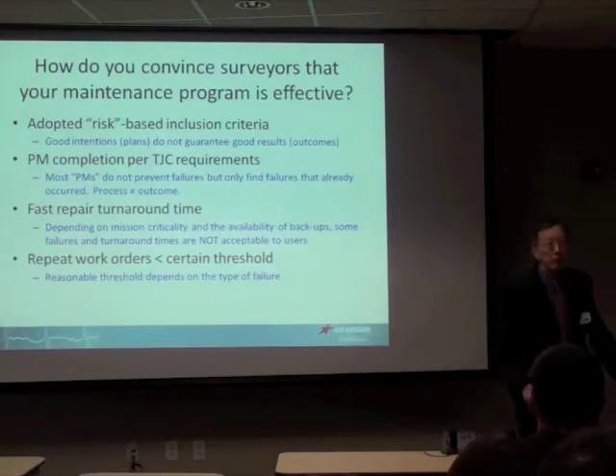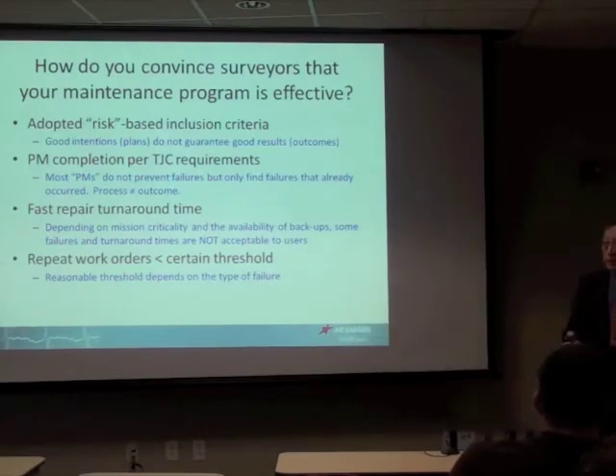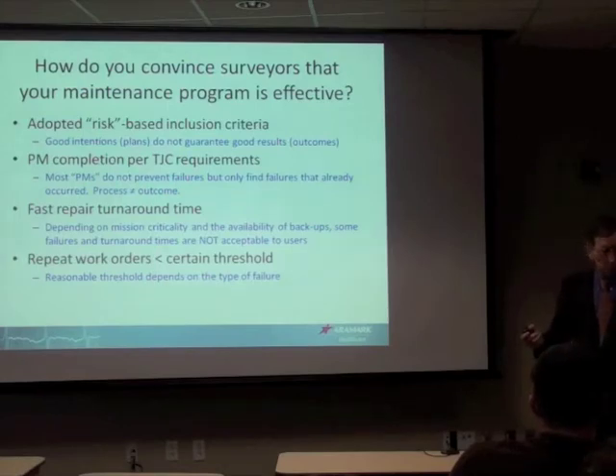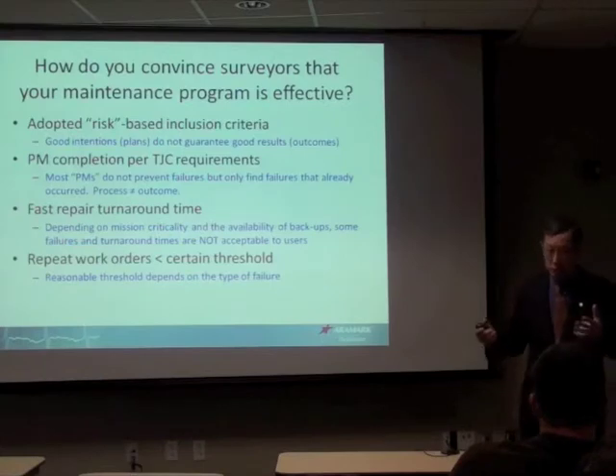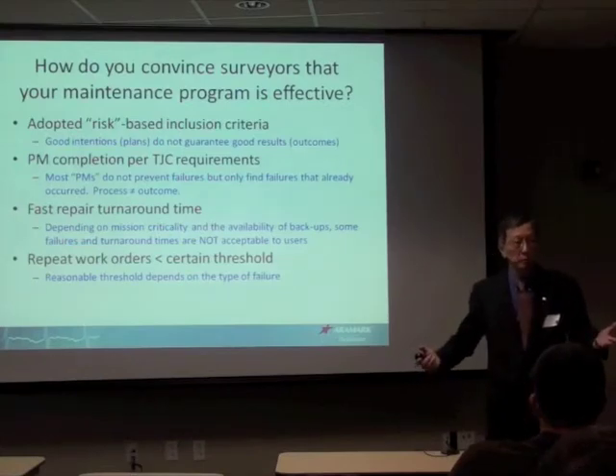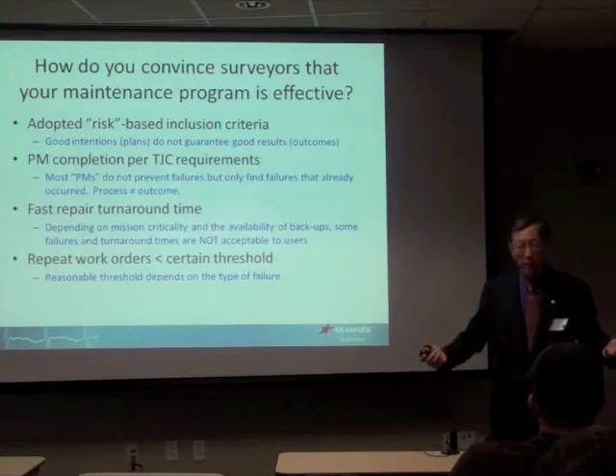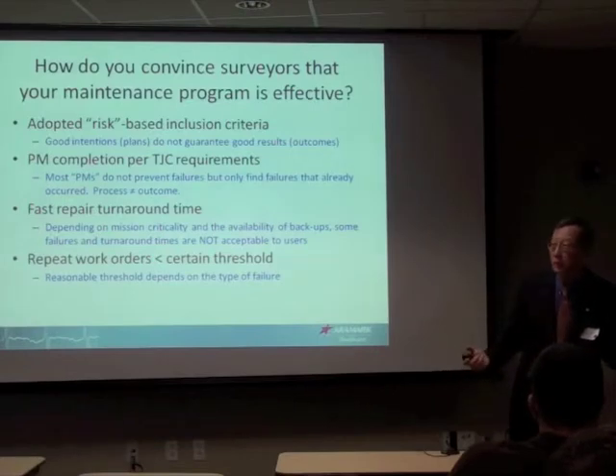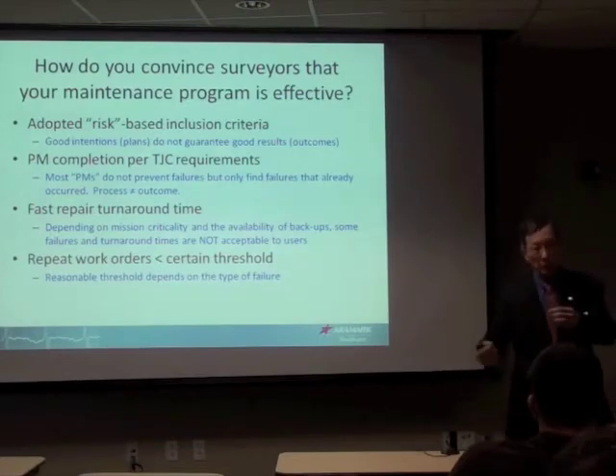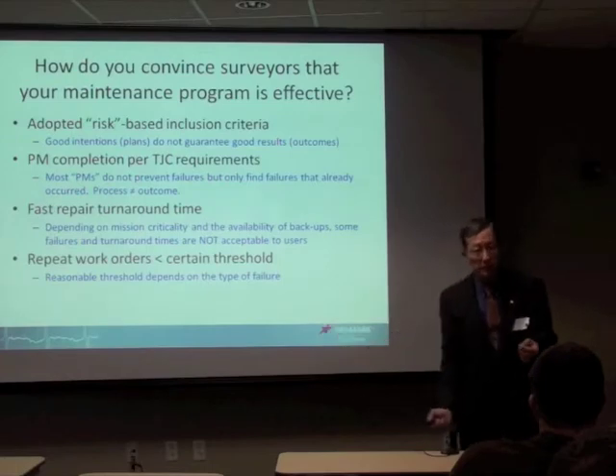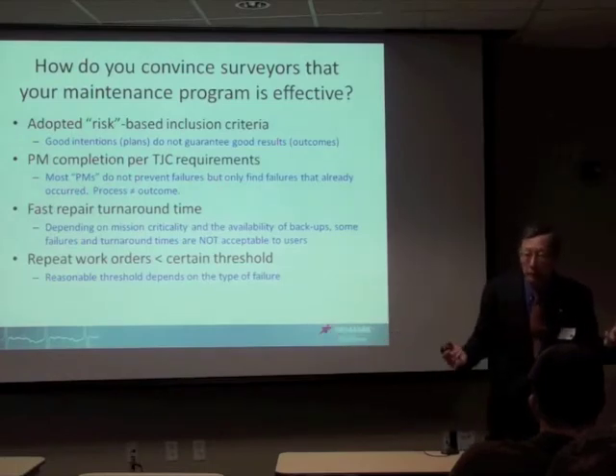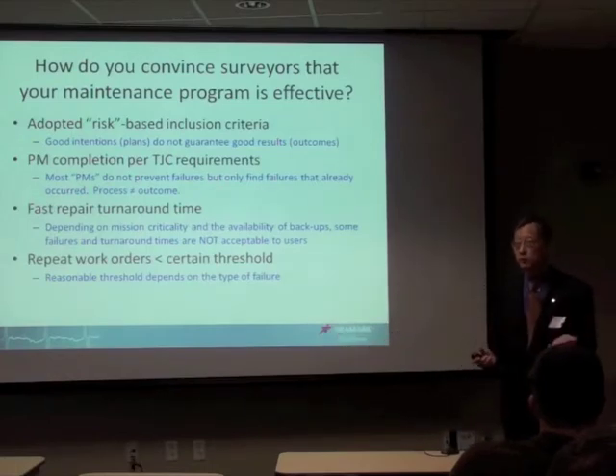We keep talking about failures here, thinking that every failure is the same. Electrical safety is an important thing, yes, but electrical safety on a ventilator, which is by definition life support equipment, is not important. Because I've yet to see a patient that can be shocked by a ventilator, because the only connection is a bunch of plastic tubing. Right? So, wait a minute, that's not really an important failure.